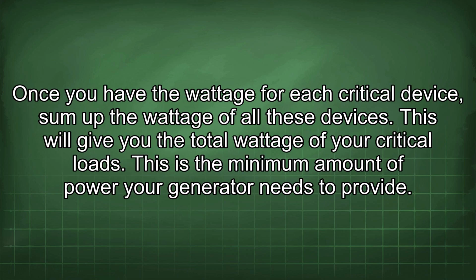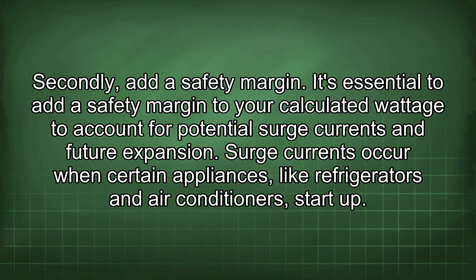Once you have the wattage for each critical device, sum up the wattage of all these devices. This will give you the total wattage of your critical loads. This is the minimum amount of power your generator needs to provide. Secondly, add a safety margin. It's essential to add a safety margin to your calculated wattage to account for potential surge currents and future expansion.